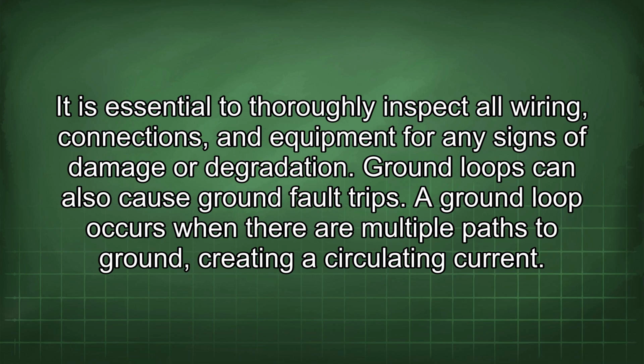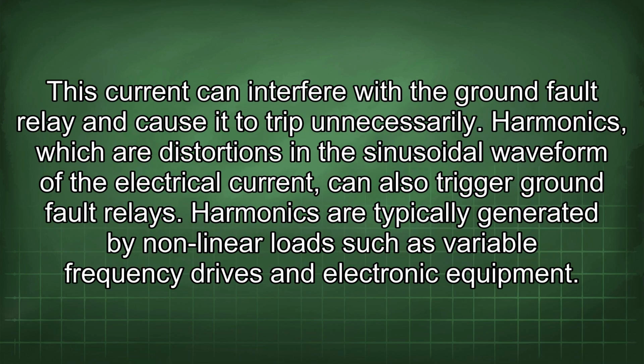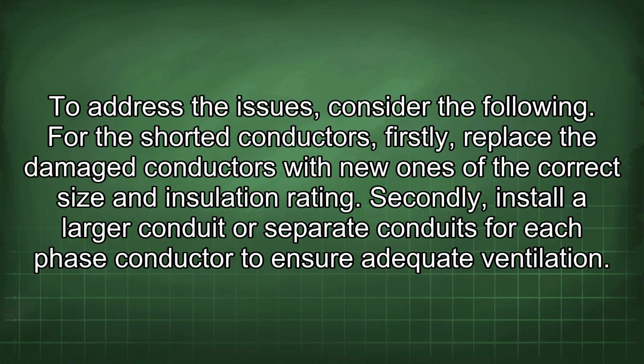A ground loop occurs when there are multiple paths to ground, creating a circulating current. This current can interfere with the ground fault relay and cause it to trip unnecessarily. Harmonics, which are distortions in the sinusoidal waveform of the electrical current, can also trigger ground fault relays. Harmonics are typically generated by nonlinear loads such as variable frequency drives and electronic equipment. To address the issues, consider the following.